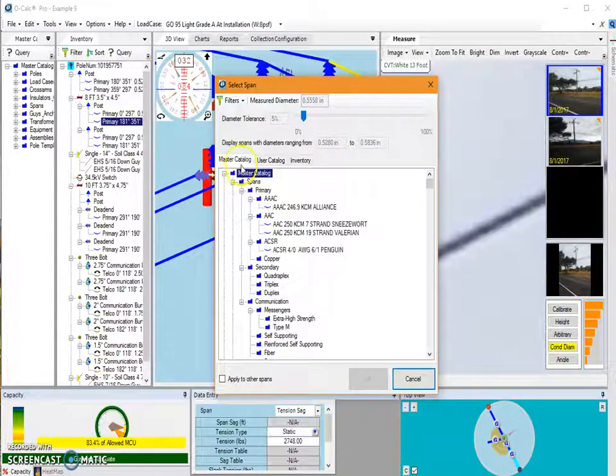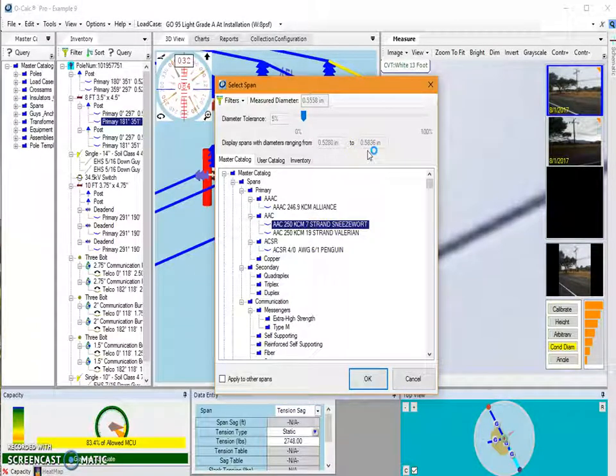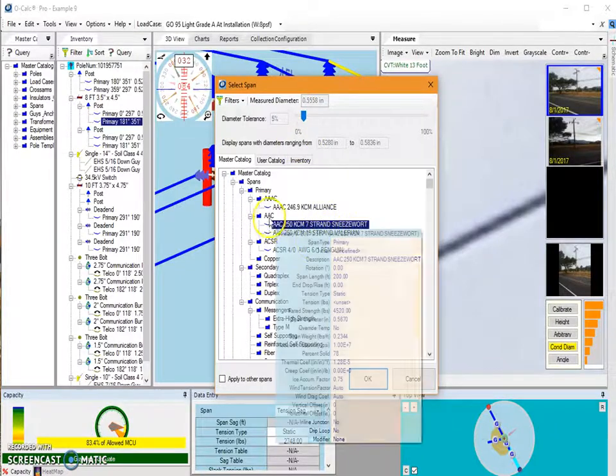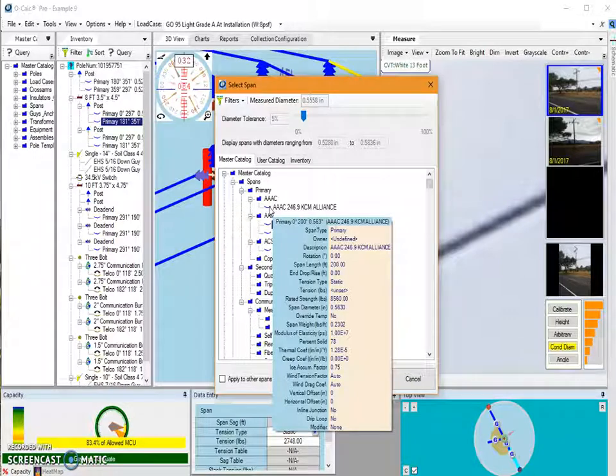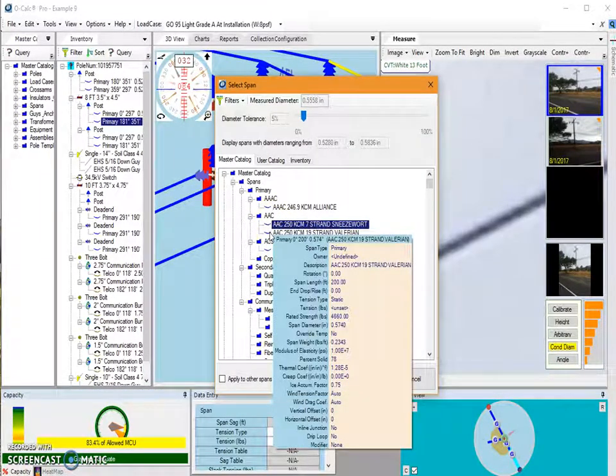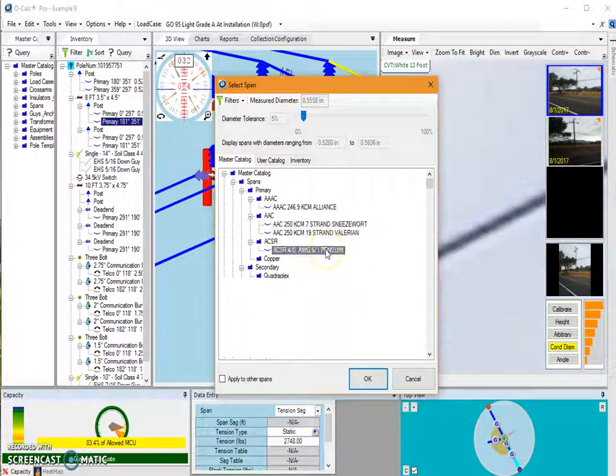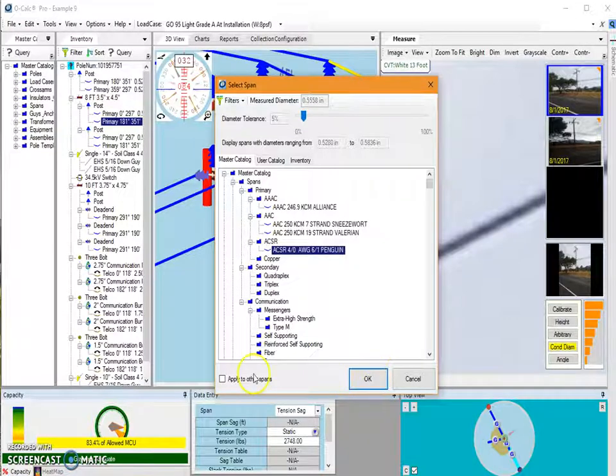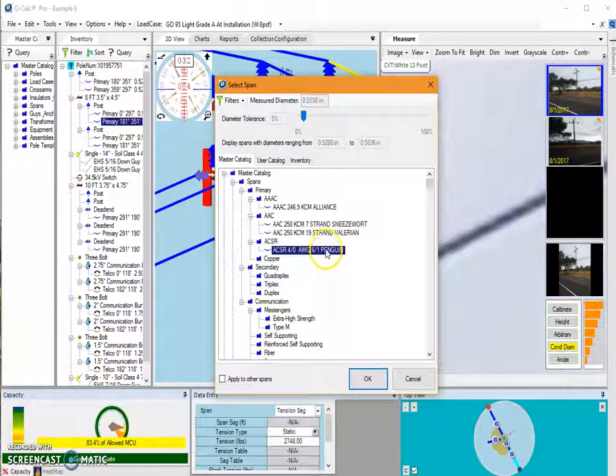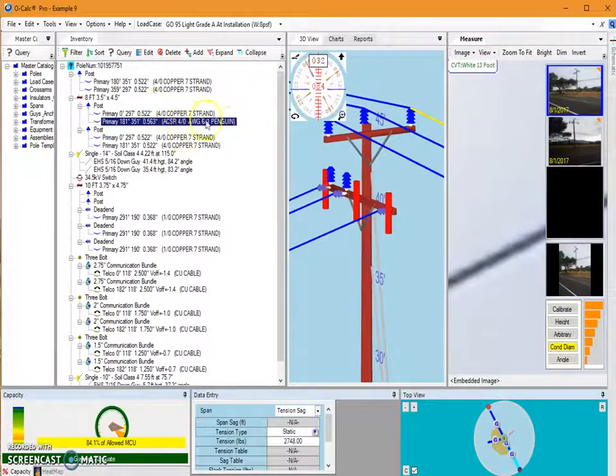Underneath, it shows the master catalog filtered to only show those spans — these four are the only ones that fit this criteria, so I can safely assume my primaries are one of these types. Hovering over the symbol, I can see the span diameters: 0.56, 0.56, 0.57, and 0.56 inches. I'm going to choose the ACSR 4/0 span and select OK. You can also select Apply to Other Spans and it will replace all those other spans with this particular type, or you can select just that span and hit OK, then view your inventory list to confirm it was replaced.